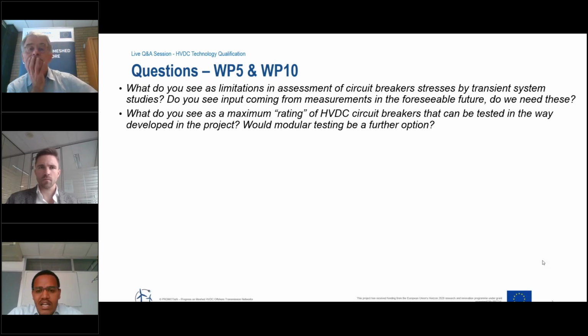But in some designs, the modular approach is only on the current paths. That means you cannot take out part of the breaker to test as a module, because some parts are rated for 500 kV, and some parts are rated for maybe lower voltage because they are divided. So you have to be careful about the design when you say modular testing. Otherwise, it would of course be one of the useful approaches to test HVDC circuit breakers.